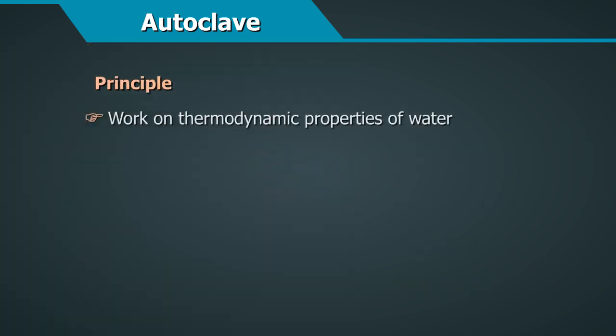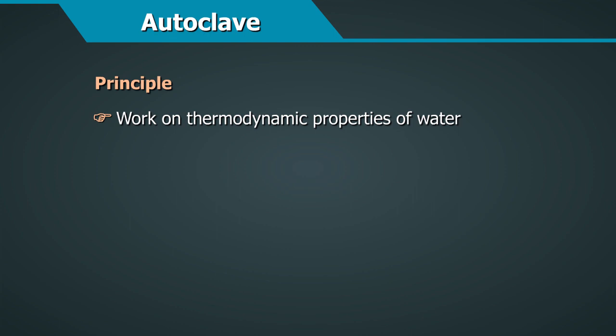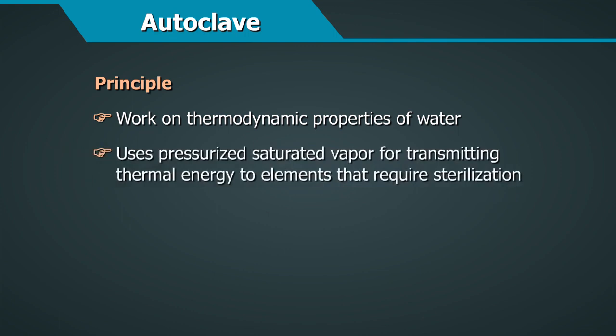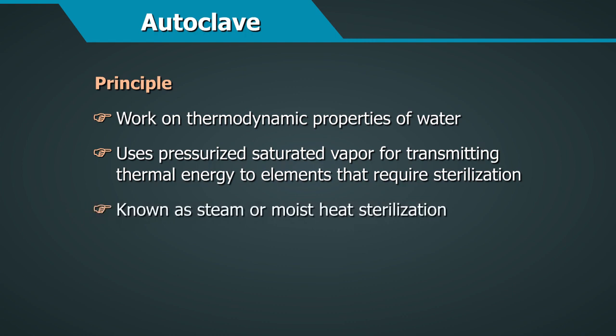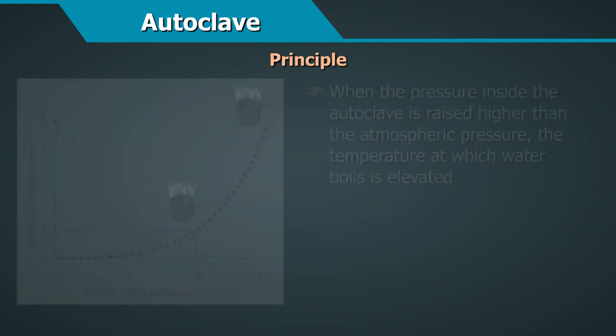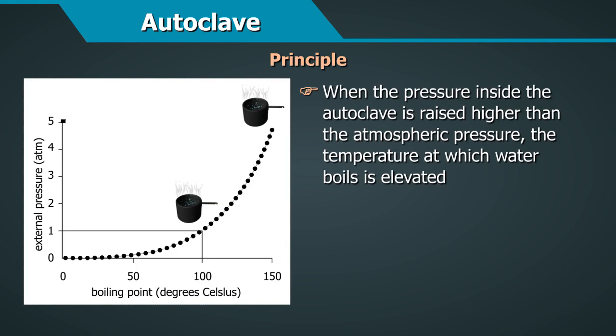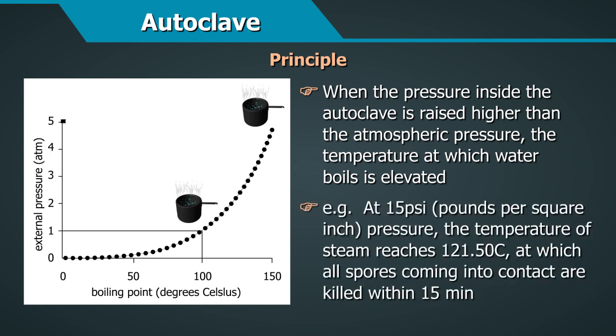Principle. Autoclaves work by taking advantage of the thermodynamic properties of water. Autoclaves use pressurized saturated vapor for transmitting thermal energy to elements that require sterilization. In general, this method is known as steam or moist heat sterilization. When the pressure inside the autoclave is raised higher than the atmospheric pressure, the temperature at which water boils is elevated. For example, at 15 psi, that is pounds per square inch pressure, the temperature of steam reaches 121.5 degrees centigrade, at which all spores coming into contact are killed within 15 minutes.